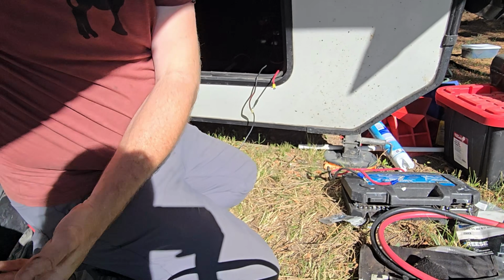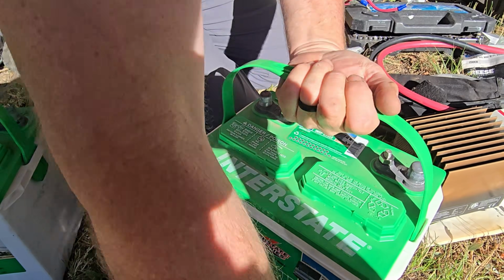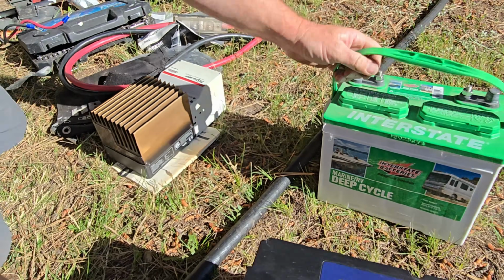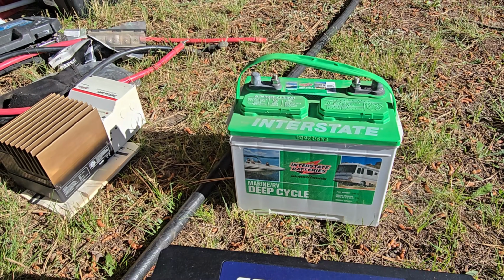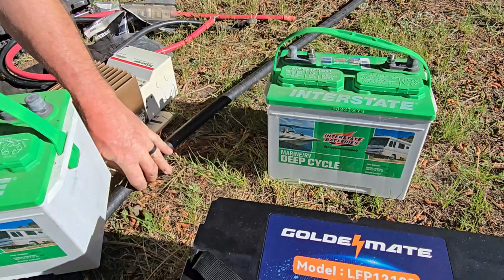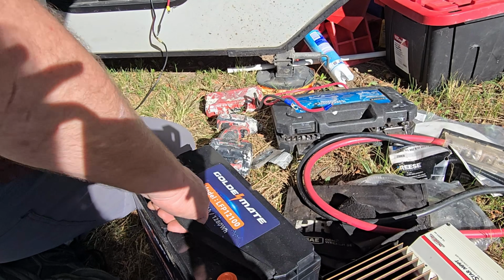And by the way, with a lead acid battery, you can't drain it all the way. You can't use its full capacity. You can only use about 50%, because if you do drain it down, you could destroy the battery. So switching to a lithium iron phosphate battery is a huge advantage as far as that goes.